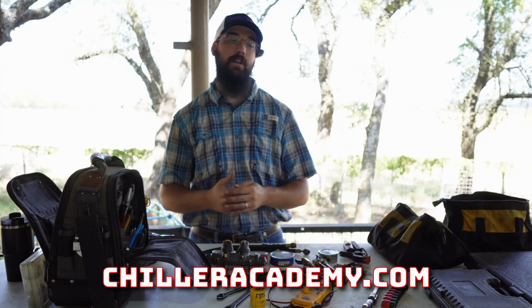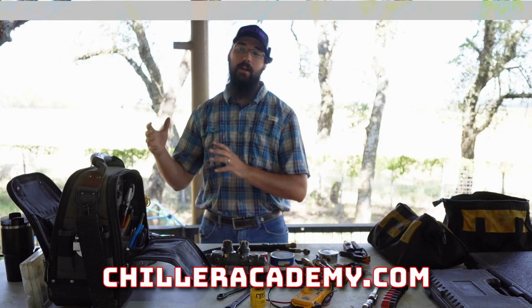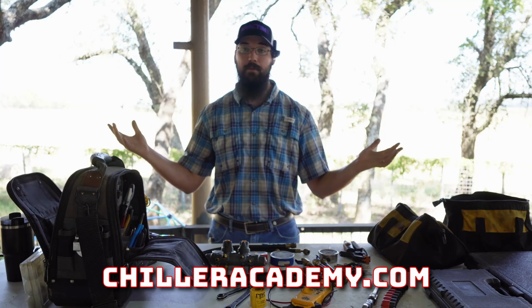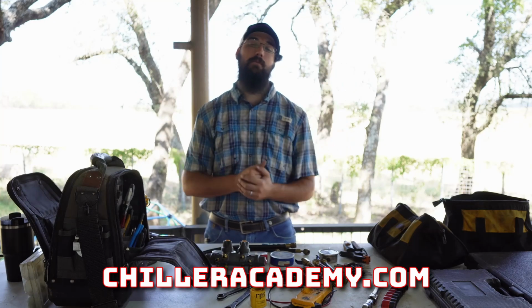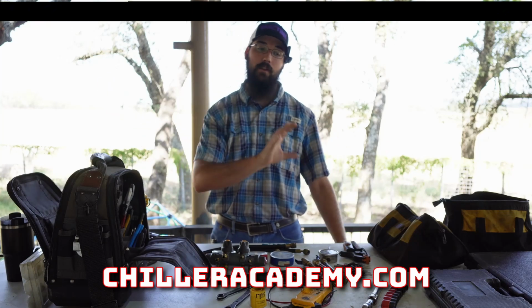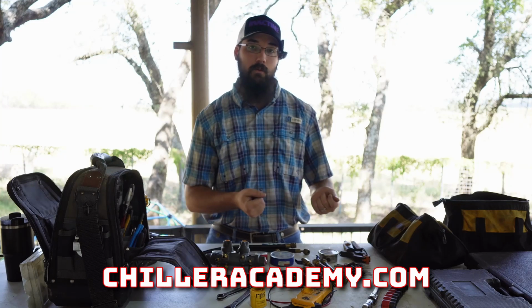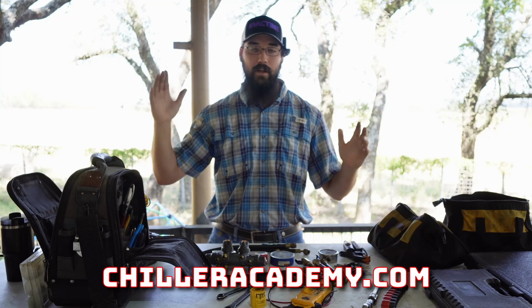So that's going to be a tool that, again, if your company doesn't invest in, you're going to have to invest in yourself, and carry those with you so that you have it if you ever need to recrimp a line and replace a feed, which happens frequently, okay? I can't tell you how many harnesses I've had to completely redo because something happened, bad connection, whatever, and they're just completely toasted. There's no salvaging that. And because of the amperages we're working with, these aren't wires that you're going to wire another crimp onto, okay? This is a home run from end to end. You've got to treat it that way.